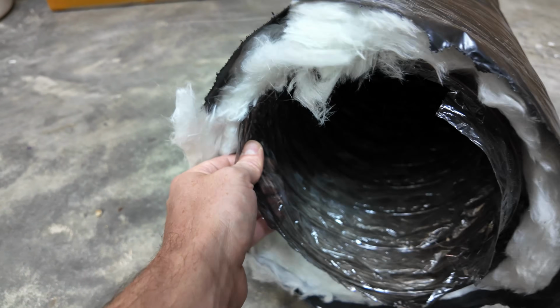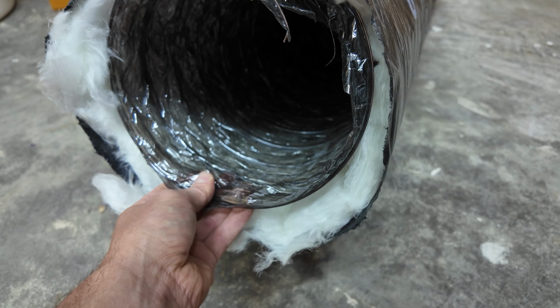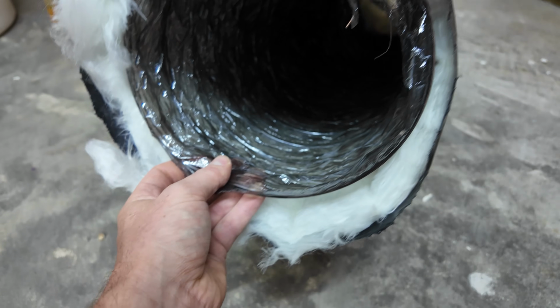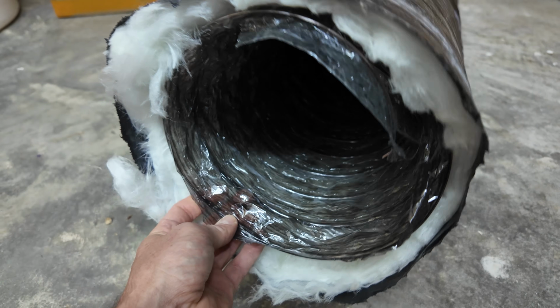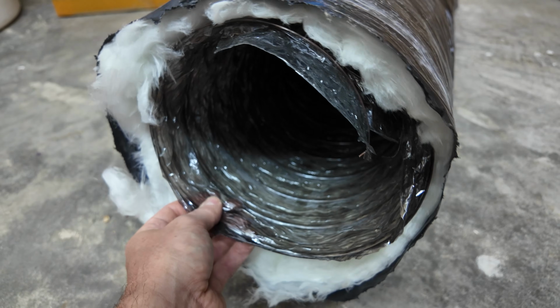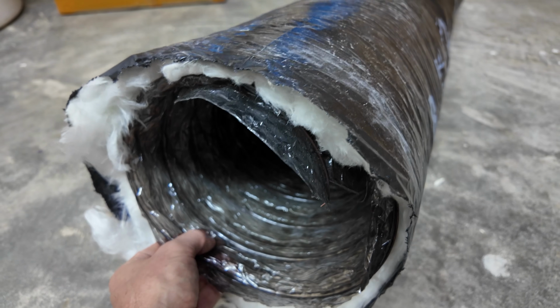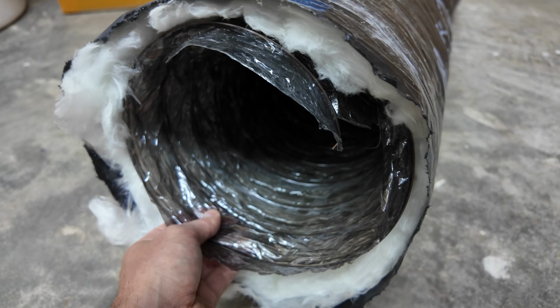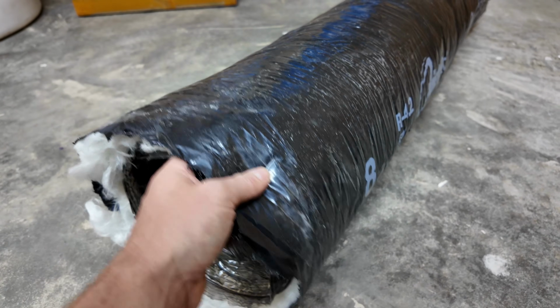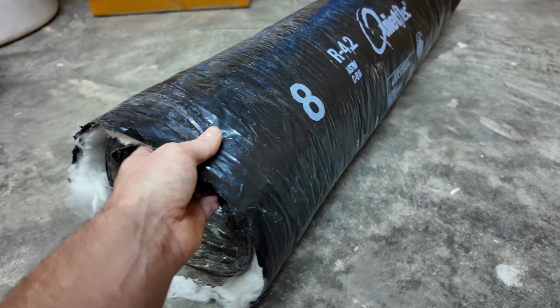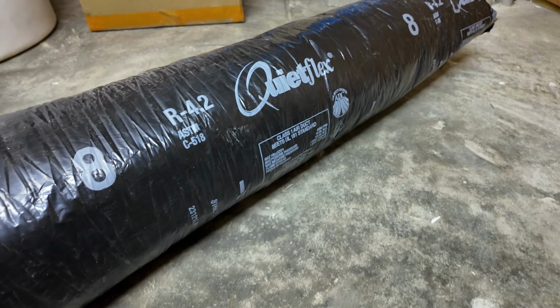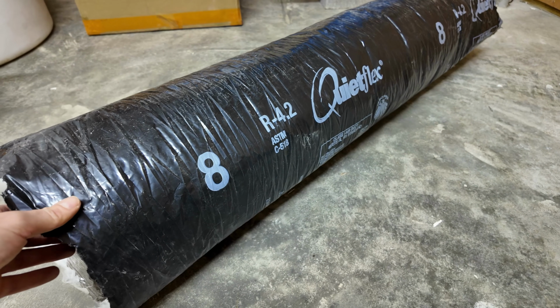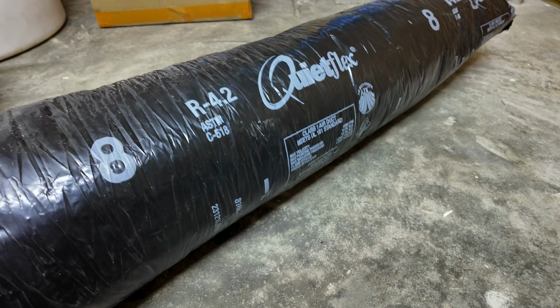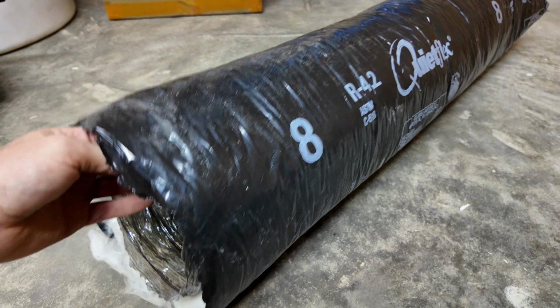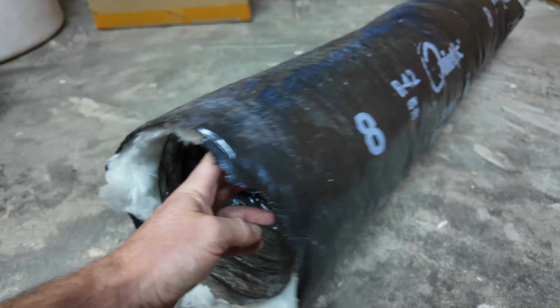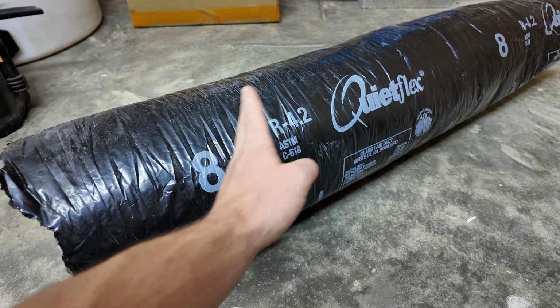Also, cleaning it, if you ever wanna get your ducts cleaned, like if they run a tool or a scope down the ducts, I just can't imagine it's gonna hold up long term. And it gathers dirt a lot more easily than a smooth piece of sheet metal will. But for vibration and sound dampening, it's fantastic, and it's pre-insulated. So there are pros and cons to everything, but on this project, I wanted to leave it in accessible areas only so it could always be replaced if ever needed. So this is a piece of 8-inch Quietflex, obviously R4.2 fiberglass insulation, and I needed to just cut about an 18-inch piece of it.